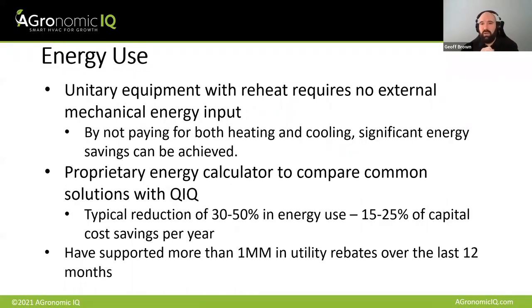Another factor is energy use. These facilities are energy pigs. Everybody's aware of it, but it matters. One of the biggest factors in energy use for unitary equipment is that properly designed unitary equipment can use 100% of the compressor waste heat, giving you the capacity to reheat for free, effectively. Anytime a compressor is operating in cooling or dehumidification, there's enough energy in that system to make up all of your reheat, meaning you're not burning BTUs on both sides. As this market matures, it's really important to stay compliant with existing rules that currently aren't being enforced.